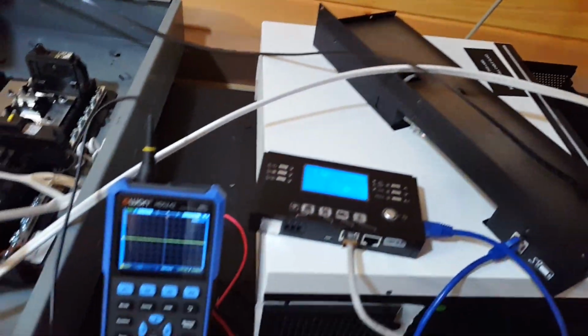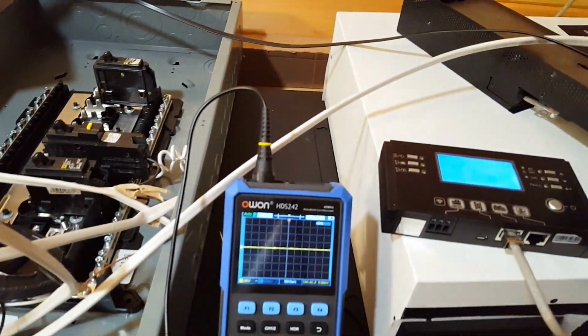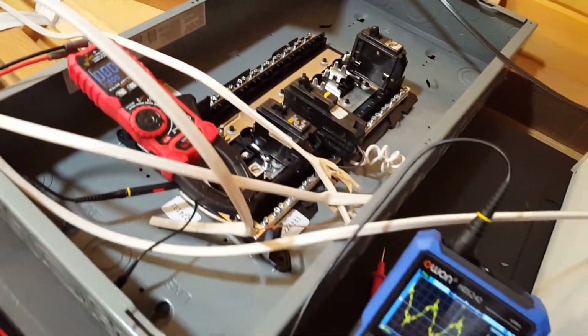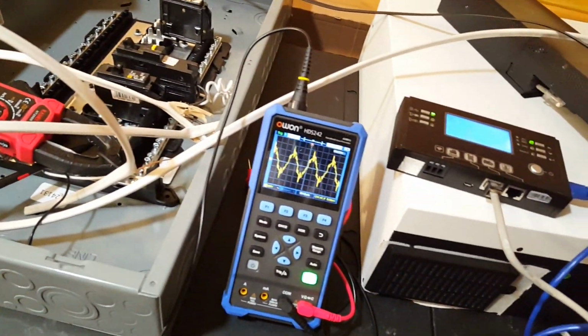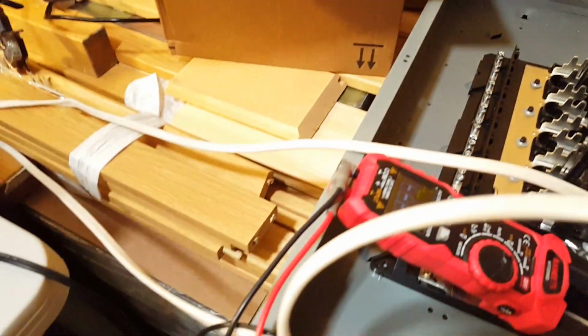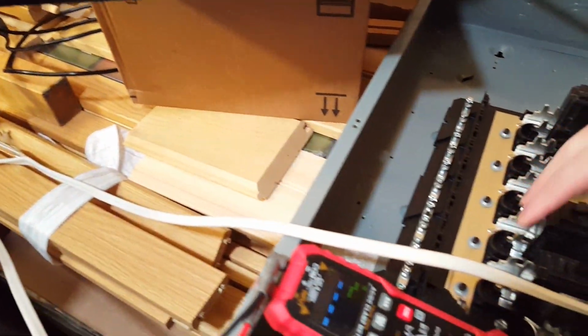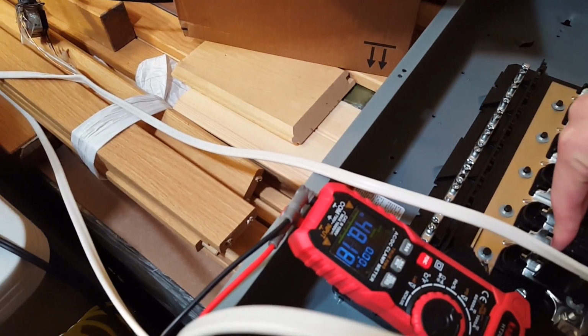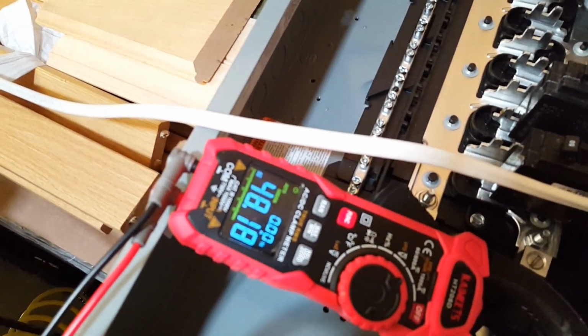I'll turn on the AC input again so we can keep the inverter on. You can see there's no sine wave. Whoops. Okay, I should have turned off the load first for the inverter to kick back on. I'm gonna try the surge test again on the AC side. 48.1 AC amps. Discharging at 20 amps from the battery.